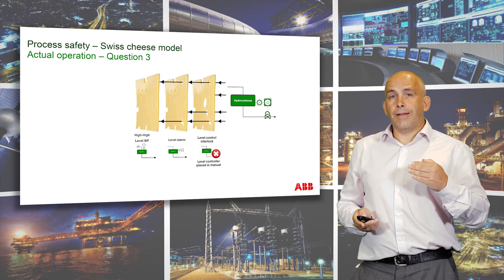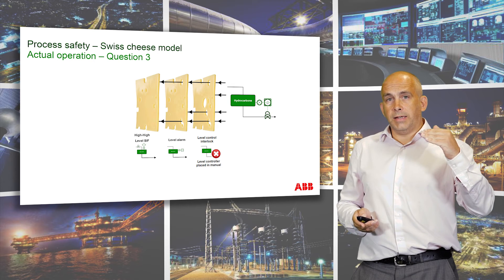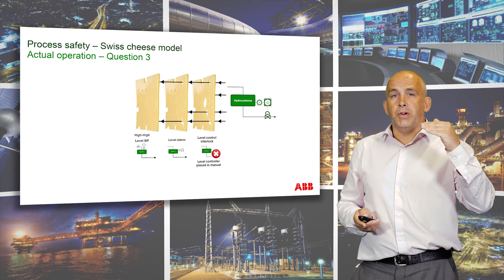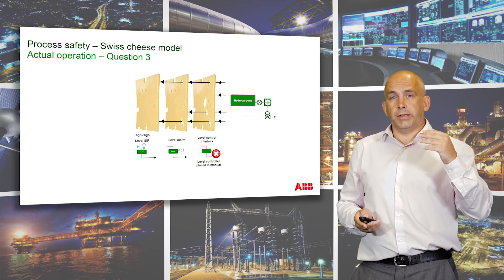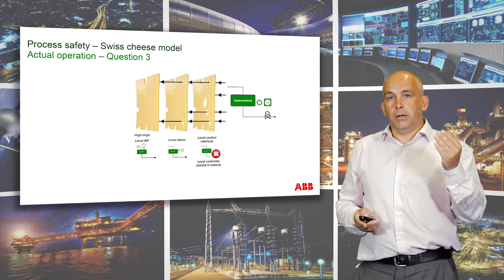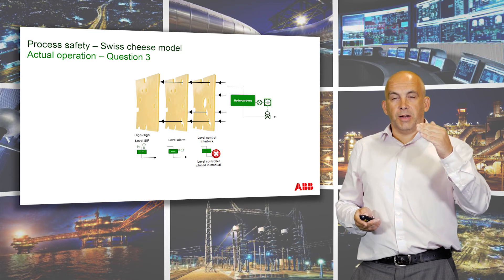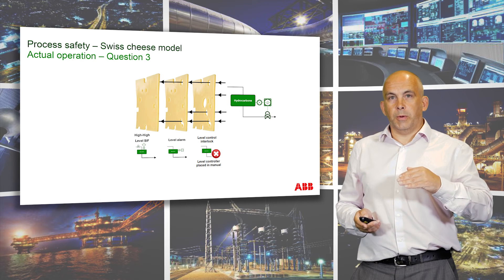As soon as that occurs, we're actually defeating that particular barrier — introducing a new hole in our Swiss cheese analogy. Then, because that controller is in manual, the level isn't controlling very well at all. Let's say now that the level is rising. It hits the alarm threshold, the alarm annunciates, the operator accepts it. Then the level goes back down again, the alarm activates again, and the operator accepts it.